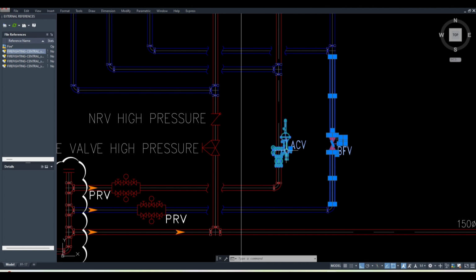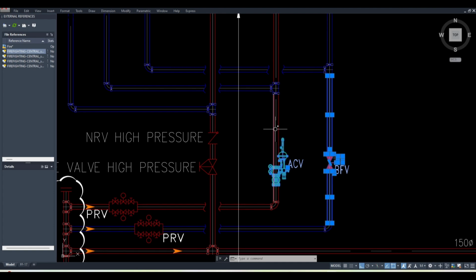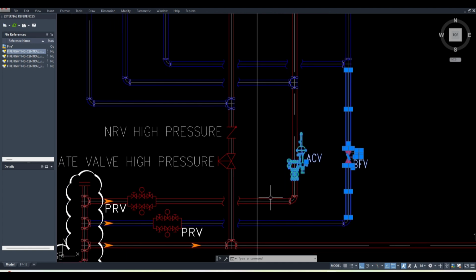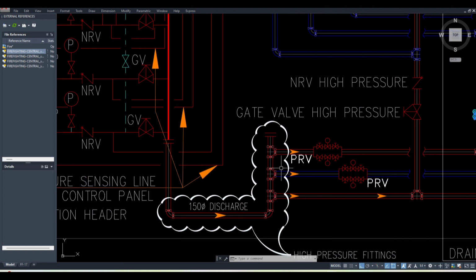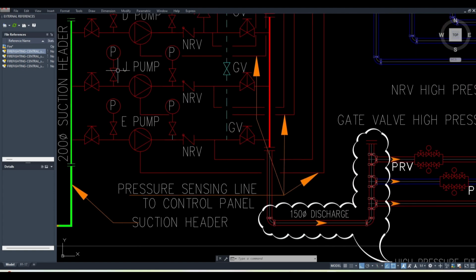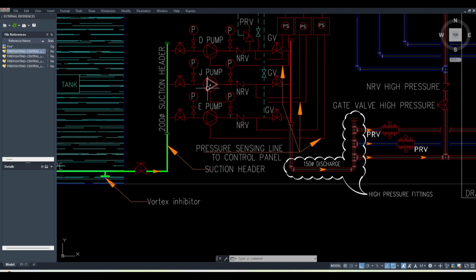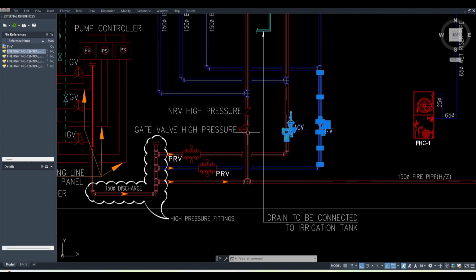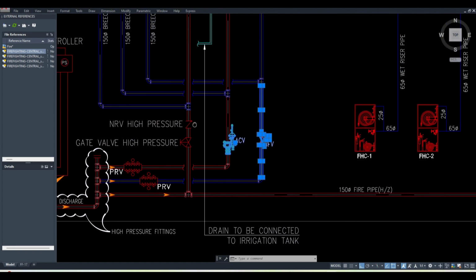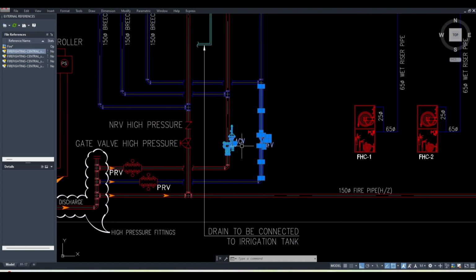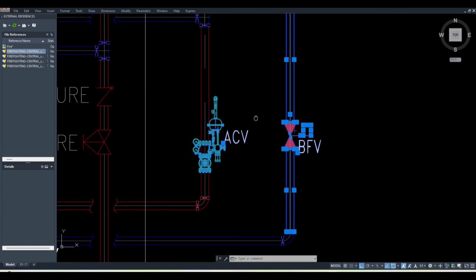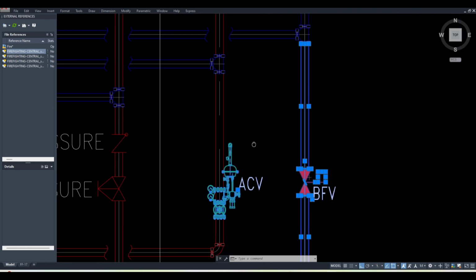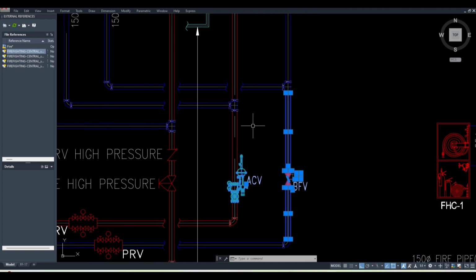to go back. Otherwise, this is a riser, this is going to a very high rising height, so water will tend to come backwards, and then it will go back, and the motor is not operating in that condition, it will start rotating, and it will go back to the tank, and it will start rotating these pumps in an opposite direction. So to prevent all these phenomena from happening, we keep one check valve. Now the name is alarm check valve because it starts alarming once this system is activated. So this is the automatic system.